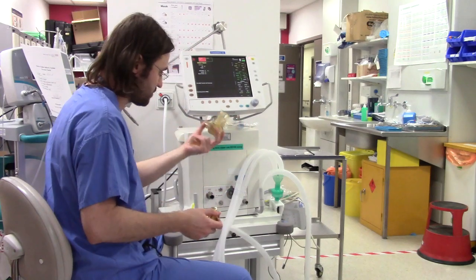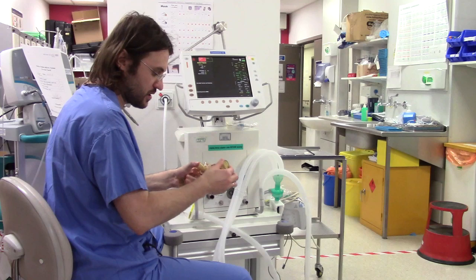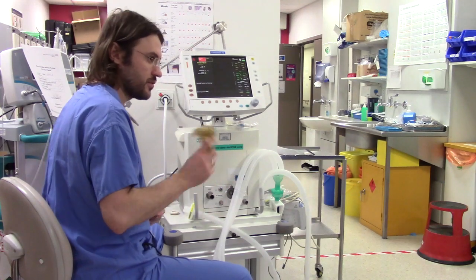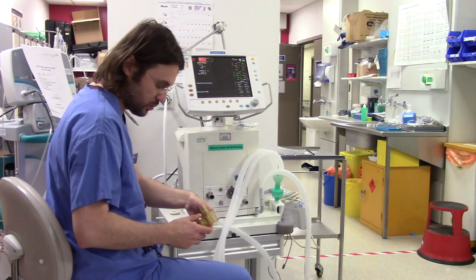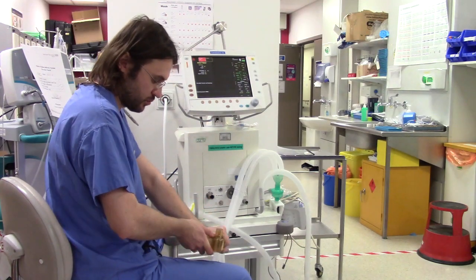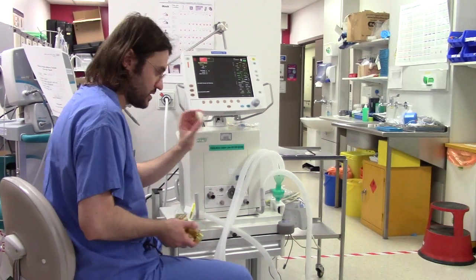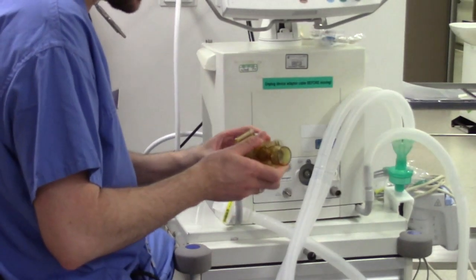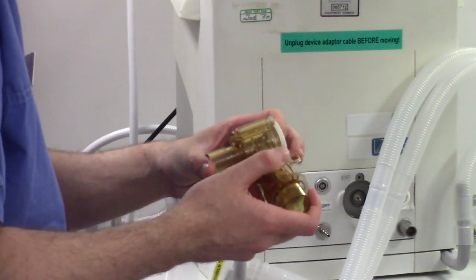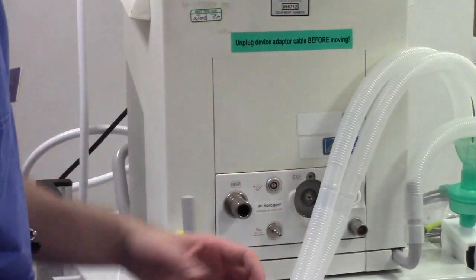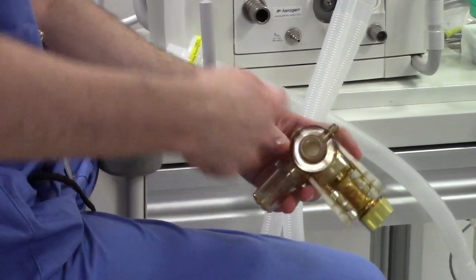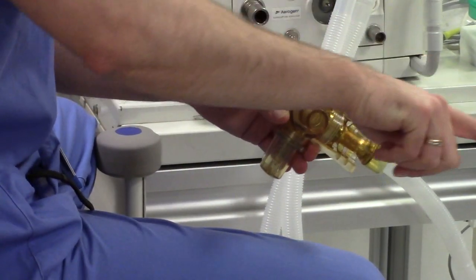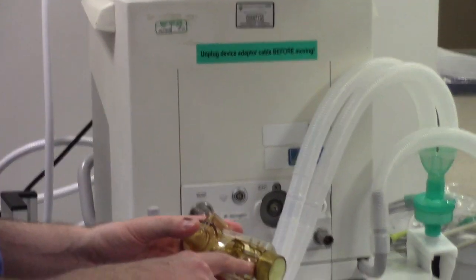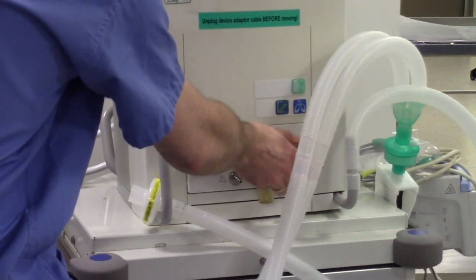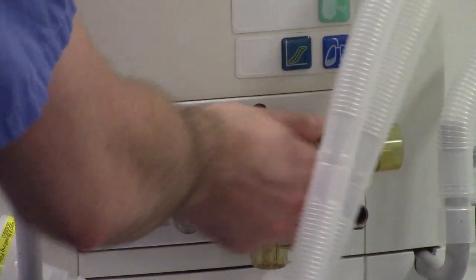So when you assemble, you put this main part of the block connected with the flow sensor. You need to hear a click in case you will need to do it from time to time, yeah. This is called water trap, which you place in here and twist like that, and it's secured. And this is diaphragm. So this diaphragm is actually giving the patient a chance to breathe out, because this pin will trigger the diaphragm, which will open or close this pathway, yeah, for the patient to breathe out through this. So we have a flow sensor in there, yeah, which will detect the flow, the volume, yeah, and so on.